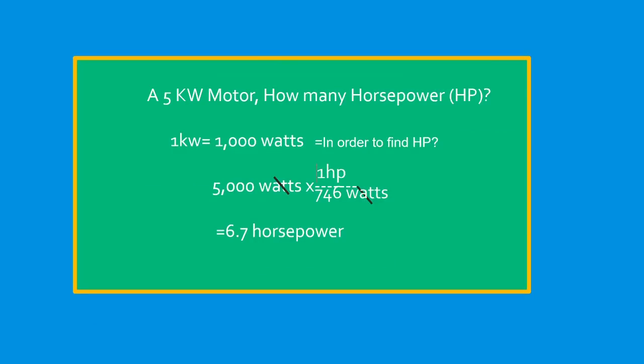Next question: a 5 kilowatt motor — how many horsepower? We know 1 kilowatt = 1,000 watts, so 5 kW = 5,000 watts. Dividing 5,000 by 746 (watts per horsepower) gives approximately 6.7 horsepower.